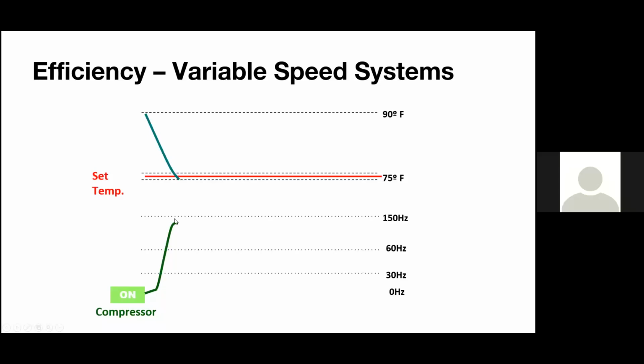And then it's going to ramp up way past the 60 hertz you might see on a traditional system. The whole goal with this is to work extra hard to get to the temperature we want to be. We want to be as comfortable as possible. That's where we're going to go, right? And where the magic happens is actually after we reach set point. As soon as we hit set point, the whole point of a heat pump system is to stay on. Typically with a conventional system, it's just going to be on-off. With VRF, we want to stay on.